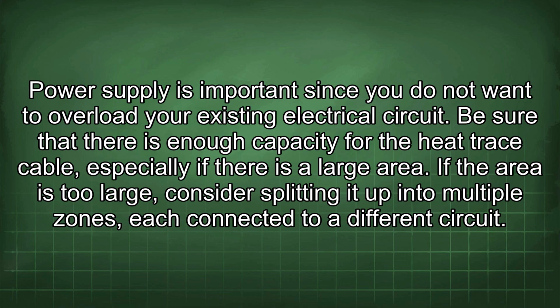Power supply is important since you do not want to overload your existing electrical circuit. Be sure that there is enough capacity for the heat trace cable, especially if there is a large area. If the area is too large, consider splitting it up into multiple zones, each connected to a different circuit.